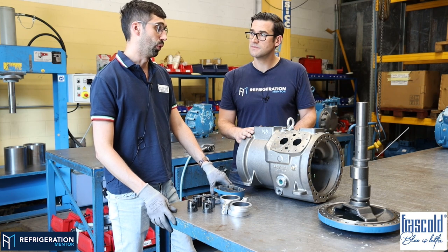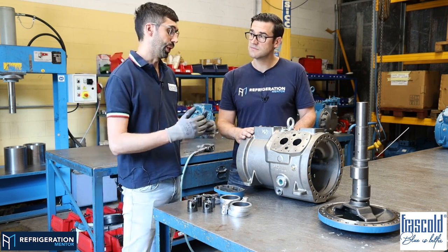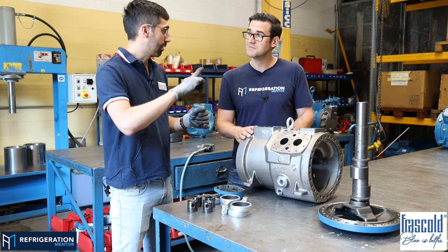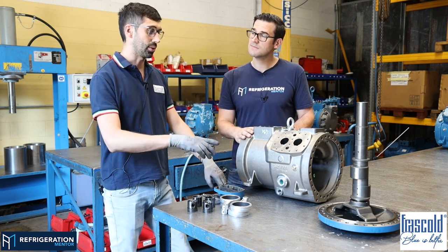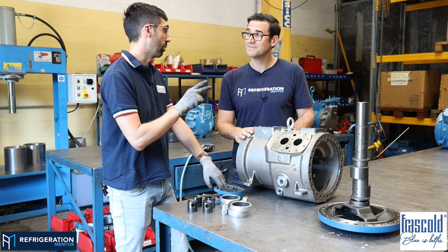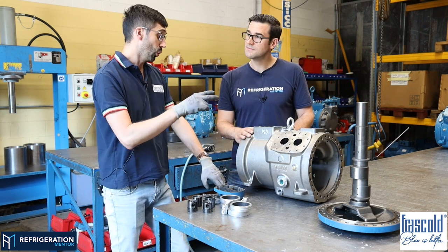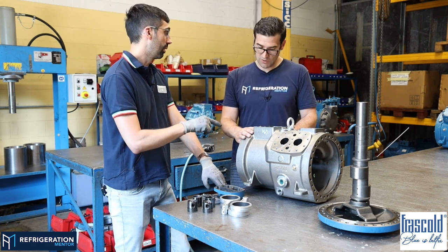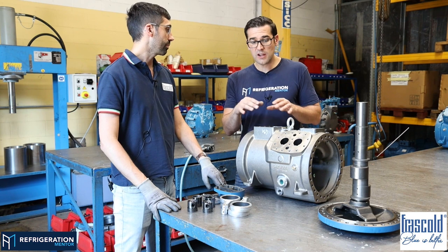For example, if you lose one phase supplying the compressor, it starts to move not smoothly, because one leg is missing. So two legs push, one leg is not working. So it starts to make the compressor vibrate. And most important is that just two phases are not able to withstand the mechanical load. So in the end, these two working phases will be overloaded and overheat. And then you encounter some electrical failure.